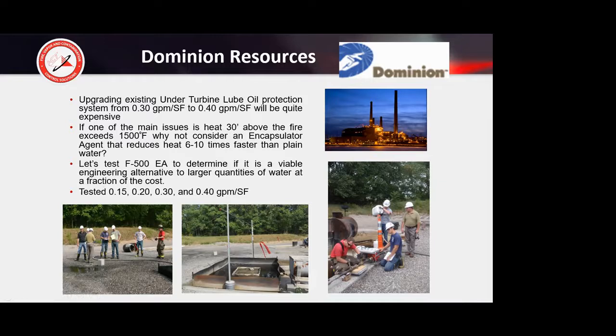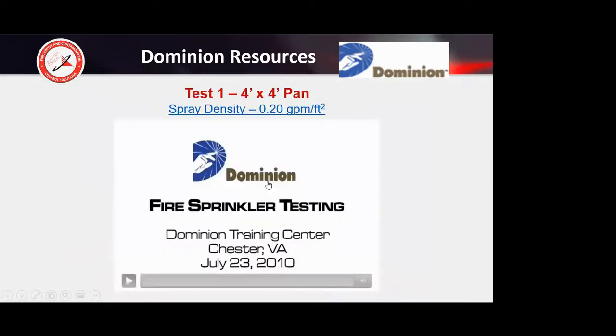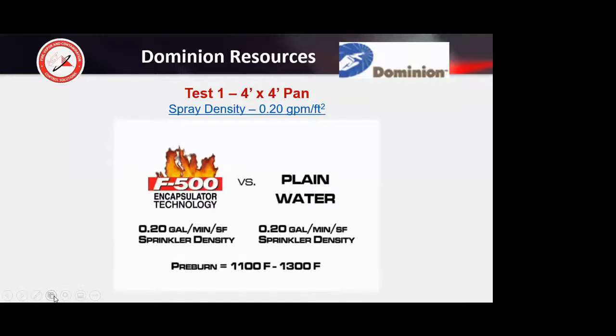Of course, me being a dumb engineer myself, I said to Mark Boone, Booney, why are you testing F500 at 0.15 and 0.2 when all of your stuff is designed at 0.3? He says, well, I really want to see what is the difference between the agent and plain water. And I don't know that I'm going to really see what I'm looking for at a higher density. So we want to test it at the lower densities to see what value the agent is actually bringing to the table.